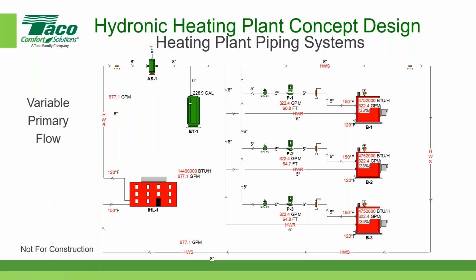I mean, most pumps have drives now. Oh no, to the boiler circ. Huh. Well, again, it depends on the characteristics of the boiler. I've shown this system to indicate that you have variable flow through the boiler. And the boiler manufacturer is going to dictate what that variable flow would be. So in this case, I just said I'm looking for a boiler that can support 322.4 gallons per minute. And that's at 100% capacity for that particular boiler.